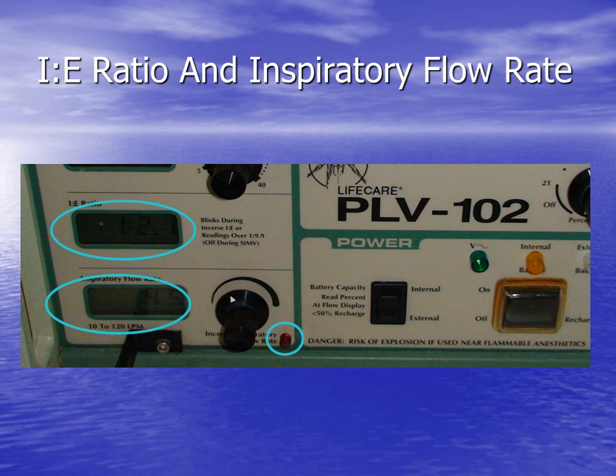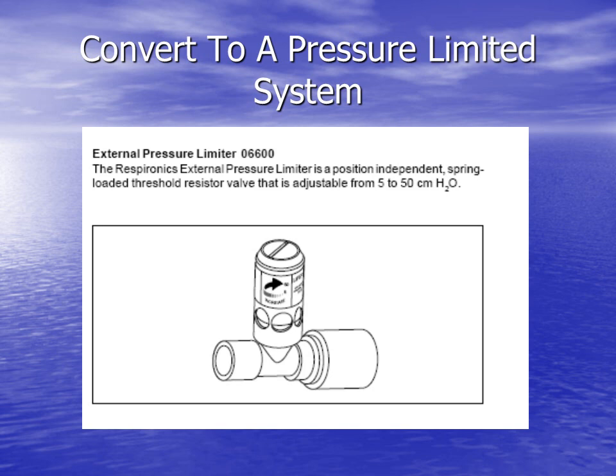This vent delivers a sinusoidal flow waveform, so if you want to know the average flow delivered to your patient, you must multiply the inspiratory flow readout by 0.637. If necessary, this volume vent can be converted to a pressure-limited vent with the addition of an external pressure limiter. It is essentially a pop-off to simulate pressure control.